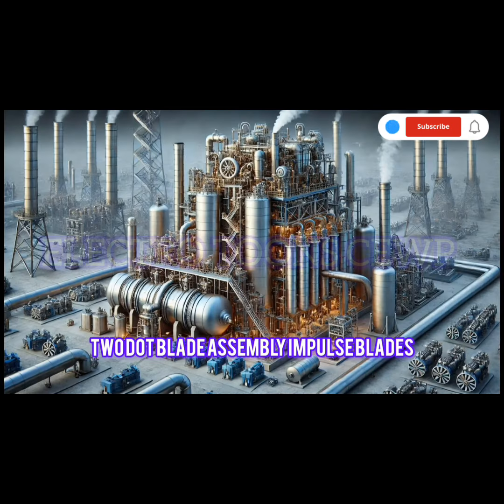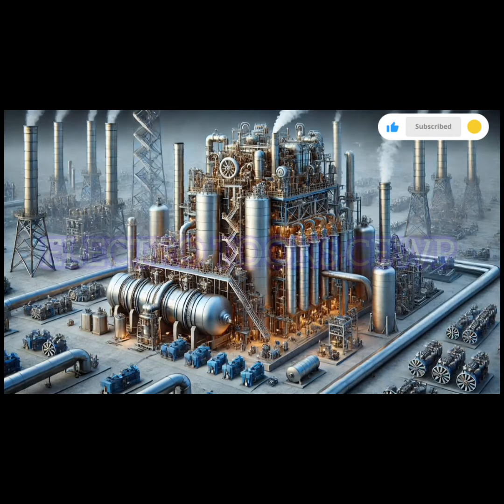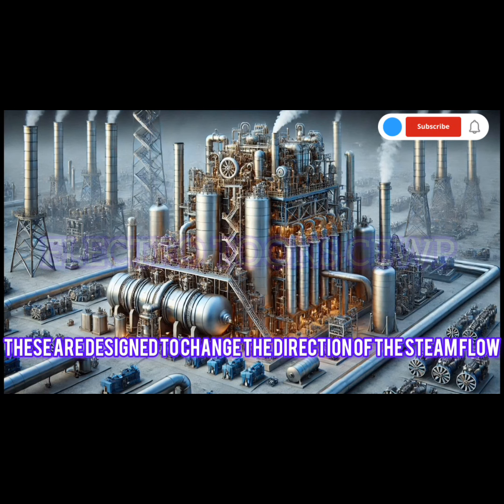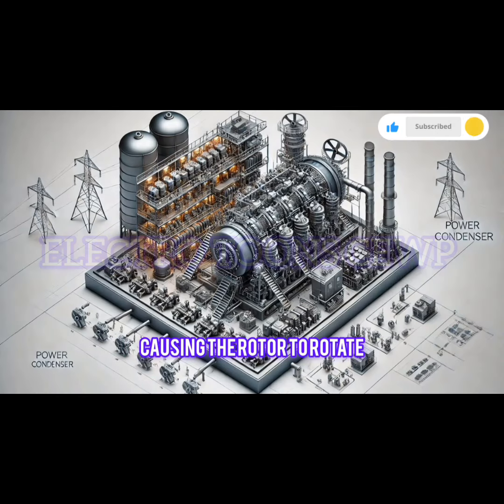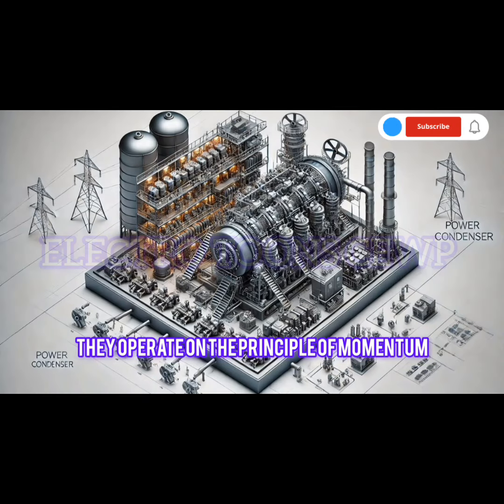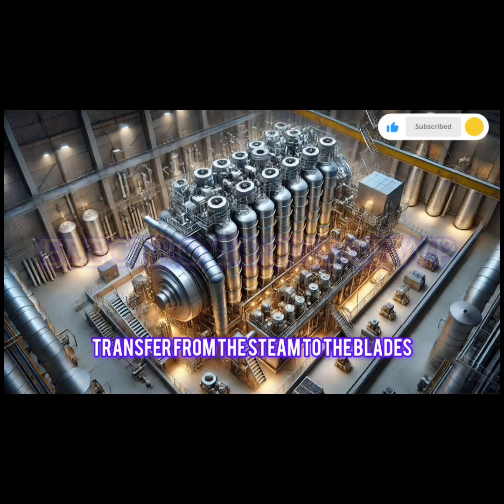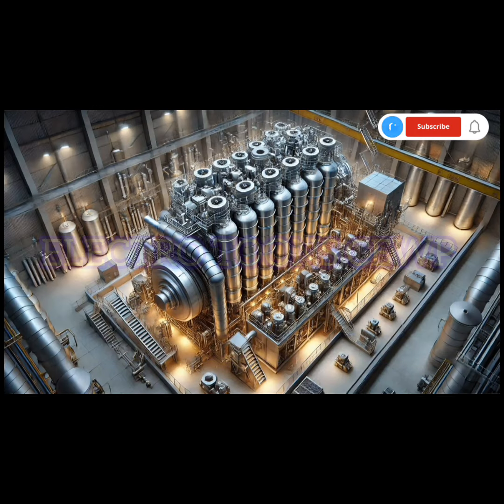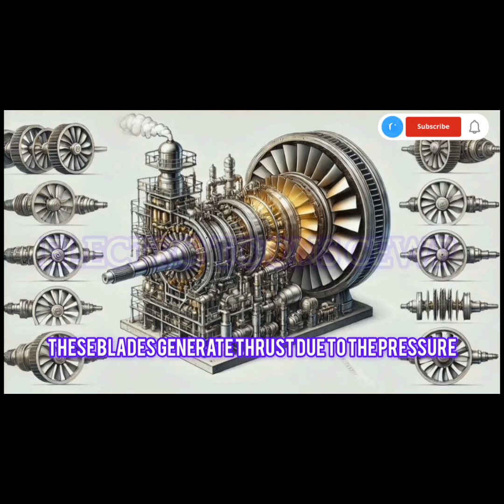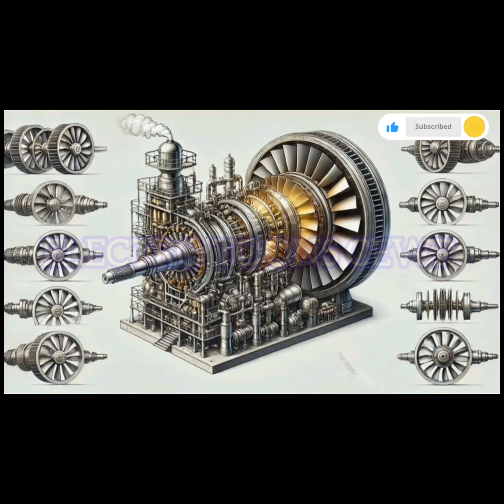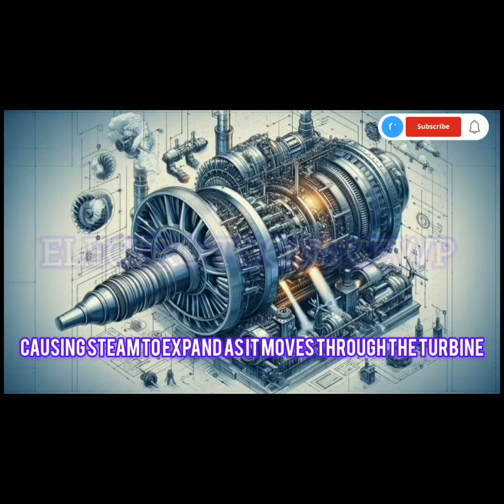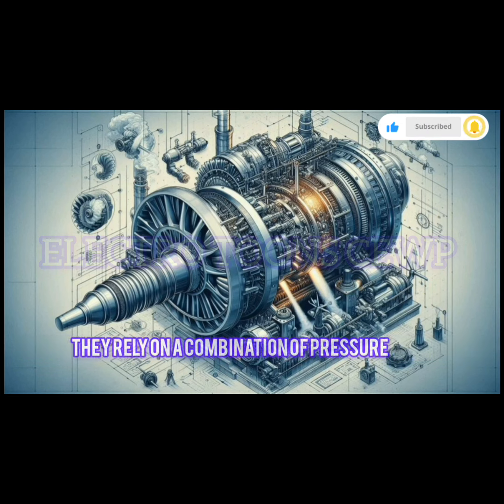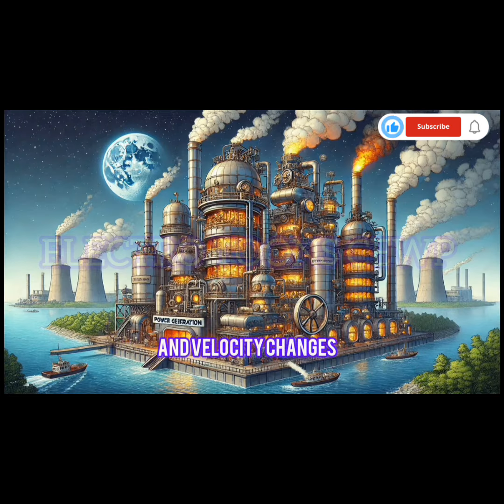2. Blade assembly. Impulse blades. These are designed to change the direction of the steam flow, causing the rotor to rotate. They operate on the principle of momentum transfer from the steam to the blades. Reaction blades. These blades generate thrust due to the pressure drop across them, causing steam to expand as it moves through the turbine. They rely on a combination of pressure and velocity changes.